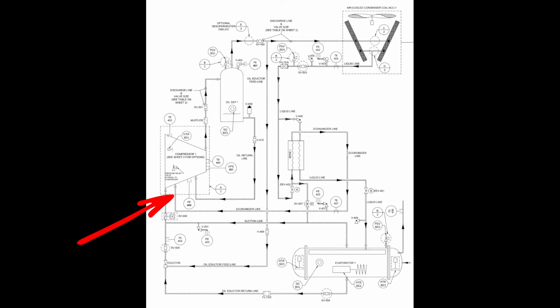Anyway, so this is where we have a standard economizer line coming into the screws, but we have an intermediate pressure here, which we also have that same basic function with the flash tank, right? So that part of the process hasn't really changed. It's just that we're increasing subcooling. Instead of trying to use a flash tank, we're doing a braze plate heat exchanger. We have what I would call a non-standard EXV. So this valve here does not look like a normal valve we would expect to see. It is just a little small bullet valve, if you will. But then the primary EXV is a standard EXV, and then that feeds into our evaporator.